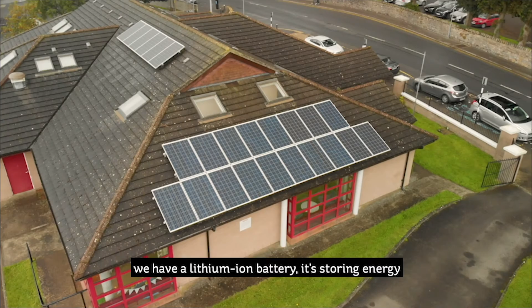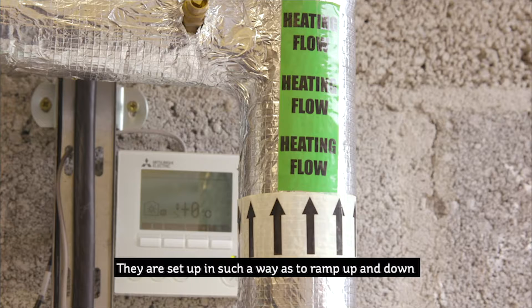We have deep retrofitted the school. We've brought the heat load down through insulation and air tightness and ventilation improvements, but we've also installed air source heat pumps. A real innovation in this case is that the heat pumps are remotely controllable to provide demand response services to the national grid. They're set up in such a way as to ramp up and down the heat load based on the demand from outside.